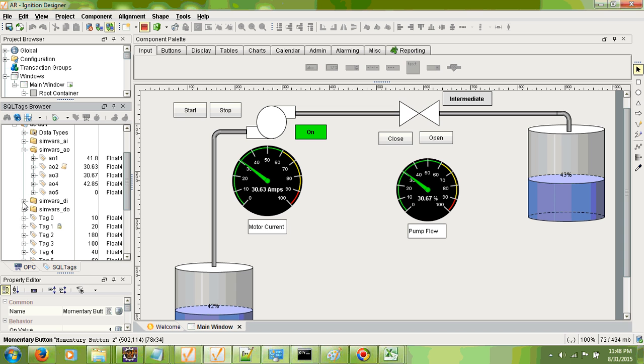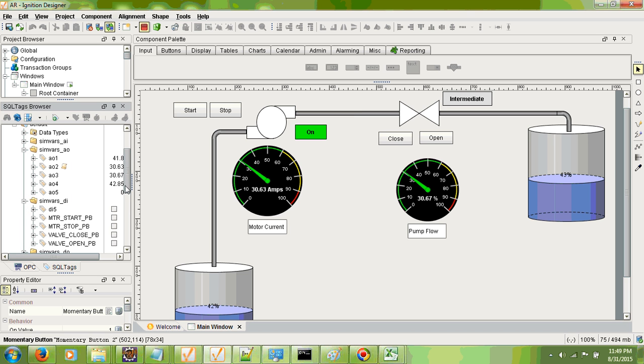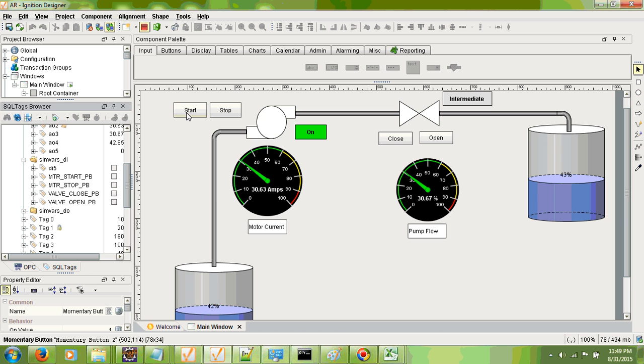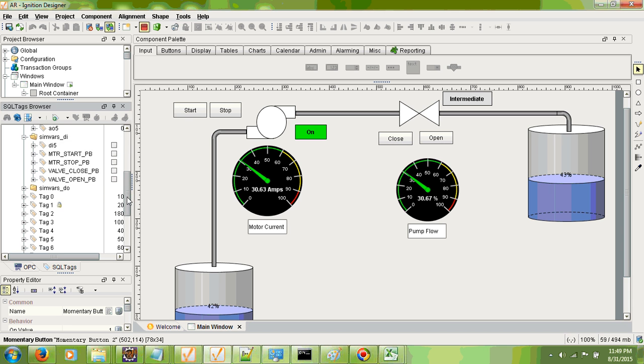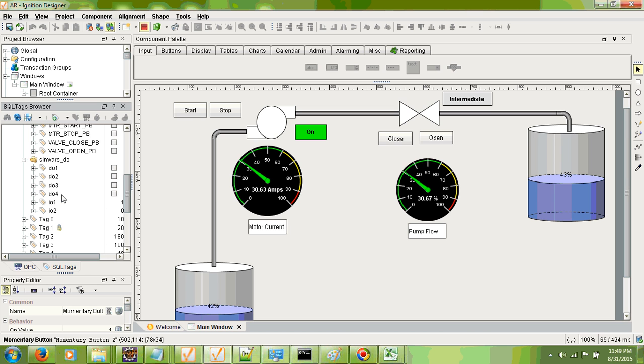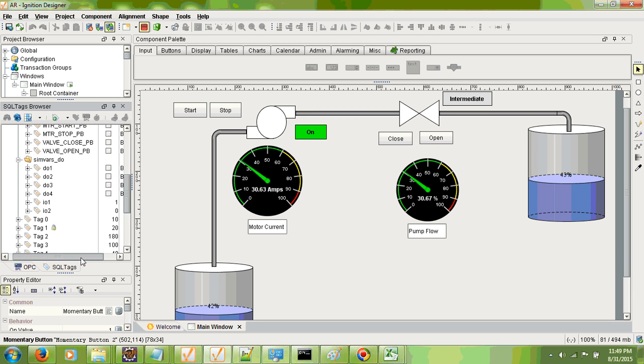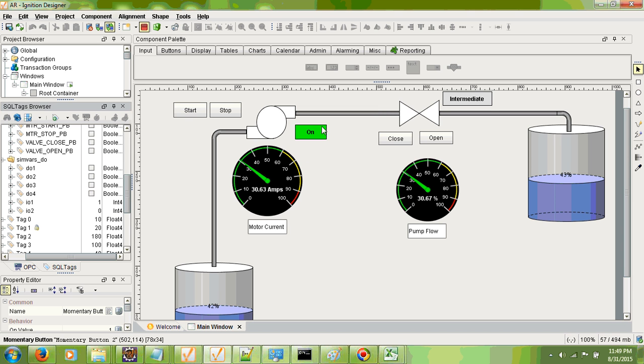Analog output 4 is tank level 2. These are all float values and the simulation is in freeze so nothing is changing. We have also defined simulation digital inputs — the pump start/motor start push button, stop push button, momentary push buttons for opening and closing the valve — and similarly a digital output folder with four digital outputs indicating checkbacks from the PLC.